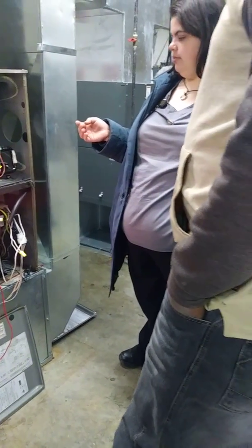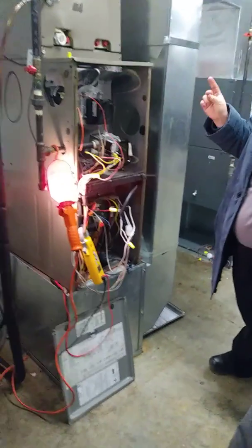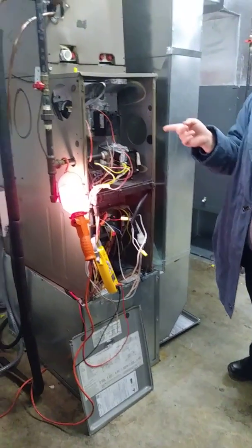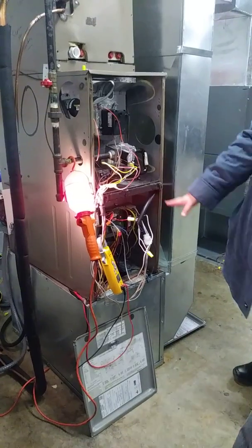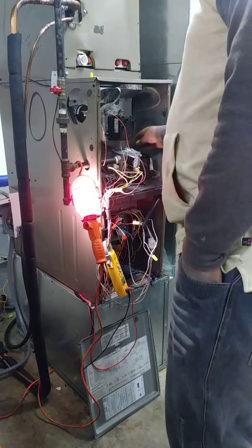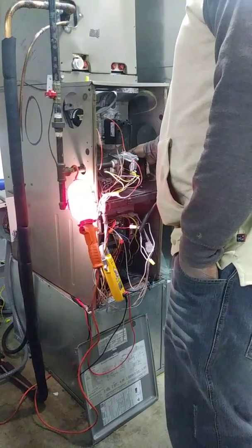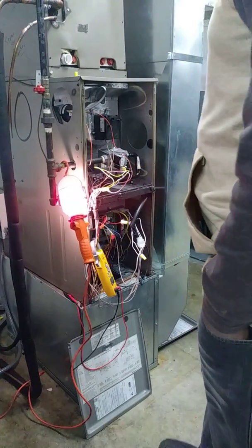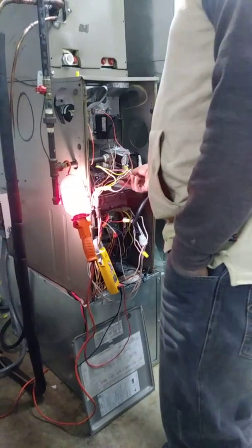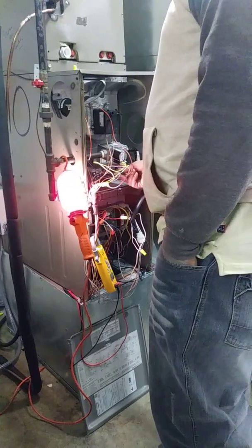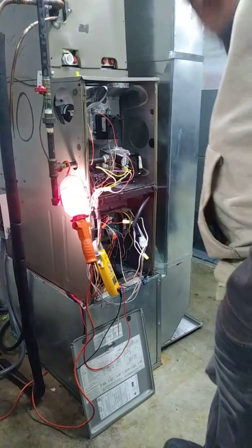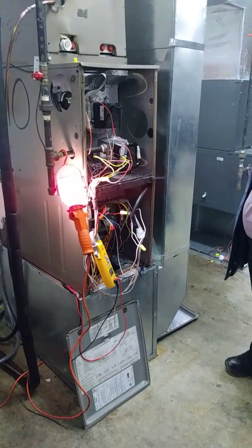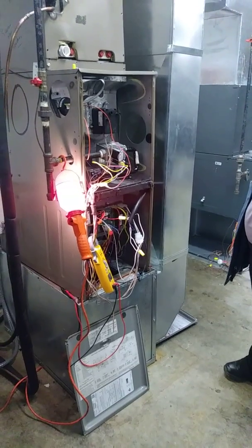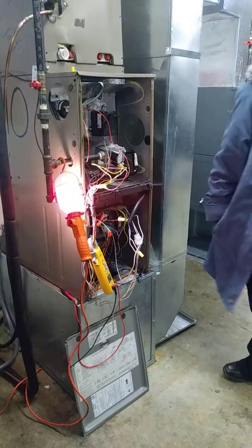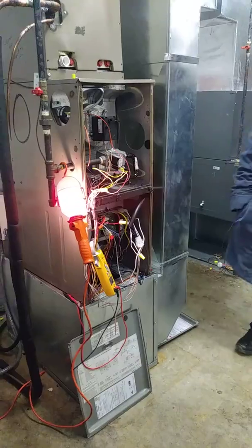Okay. But then for the hot surface igniter, the flame sensor, you check ohms. You don't check amps because it's not a motor. You have to check ohms, and you do that with the unit off and the hot surface igniter cooled down. Okay, I think I got most of that.